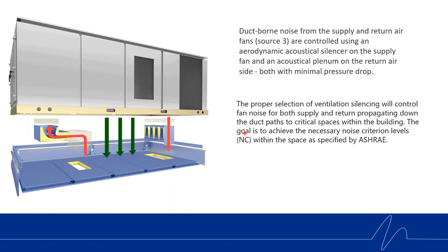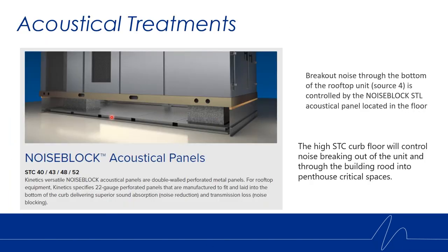In the bottom of the curb, we do have acoustical treatments. These can be laid in a factory curb — it doesn't have to be a special Kinetics isolation curb. You could have a sheet metal roof curb from the manufacturer and still put an acoustical treatment in the floor. For breakout noise through the bottom of the roof — source four — we offer our Noise Block acoustical panels, a high STC curb floor that controls noise breaking out of the unit through the building roof into the penthouse and critical spaces. These are made with double-walled perforated metal panels and come in STC ratings of 40, 43, 48, and 52.